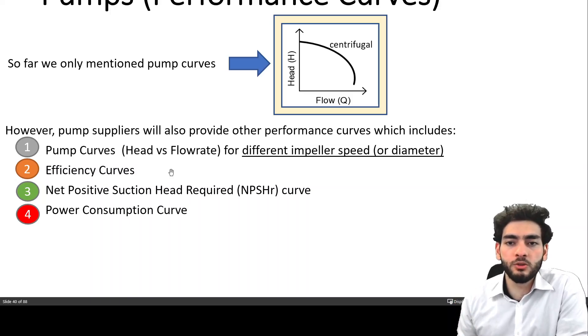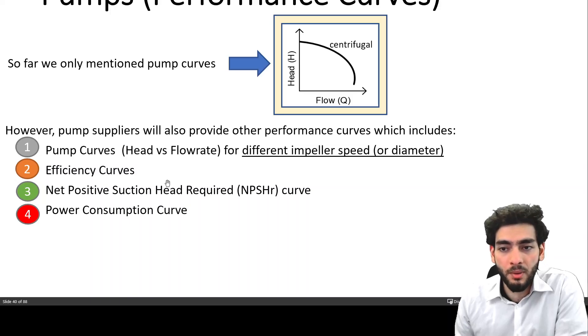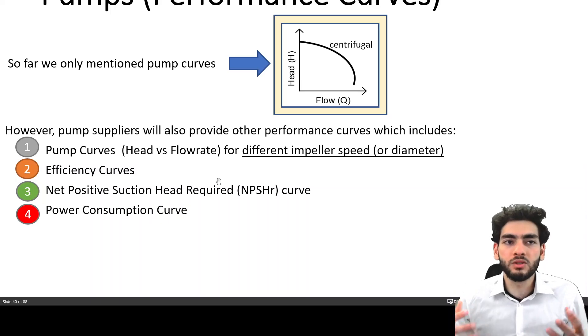The pump supplier should also provide you efficiency curves of the pump, and they should provide you with a net positive suction head requirement curve. We're going to talk about NPSHR, NPSH, in this chapter in another video, and they should also provide you with power consumption curves, which will help you select the motor.